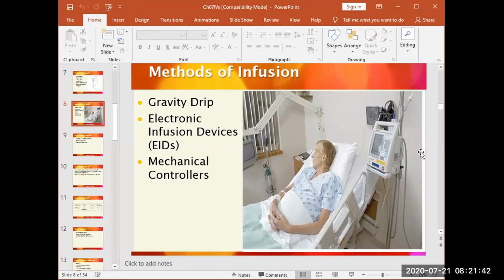Mechanical controllers measure the amount of solution delivered and depend on gravity to deliver the infusion, which is not a problem because gravity is the same everywhere on Earth. But if you do have to go into space, bear in mind that there could be a little variation on your flow. So EIDs, sometimes called pumps, use positive pressure to deliver the solution.